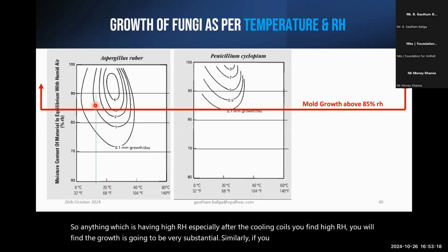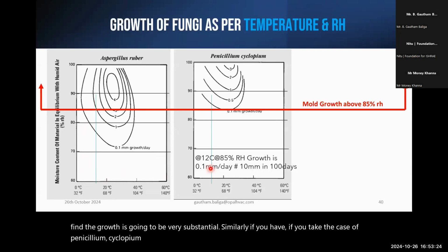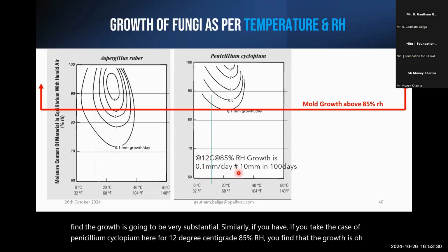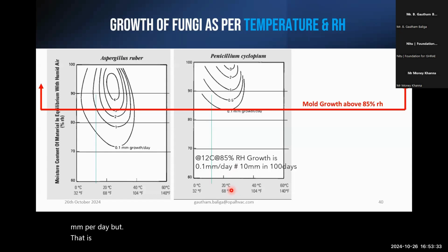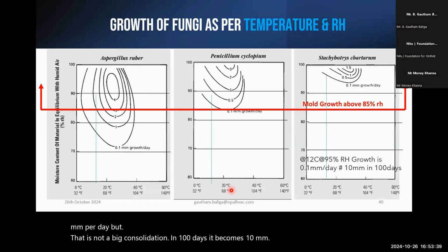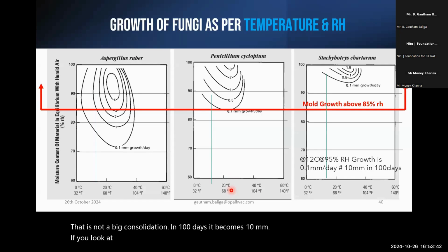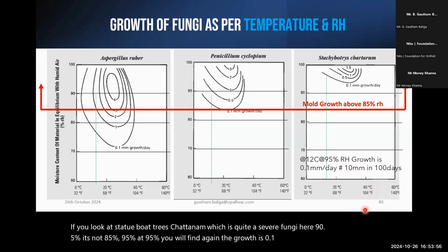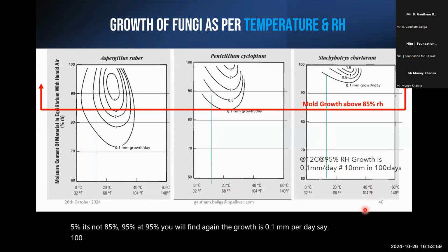Similarly, if you take the case of Penicillium cyclopium, here for 12 degrees centigrade, 85% RH, you find that the growth is 0.1 mm per day. But that's not a big consolation. In 100 days, it becomes 10 mm. If you look at Stachybotrys chartarum, which is quite a severe fungus, here at 95%, it's not 85%, 95%, you'll find again the growth is 0.1 mm per day. Say 100 days, it becomes 10 mm.